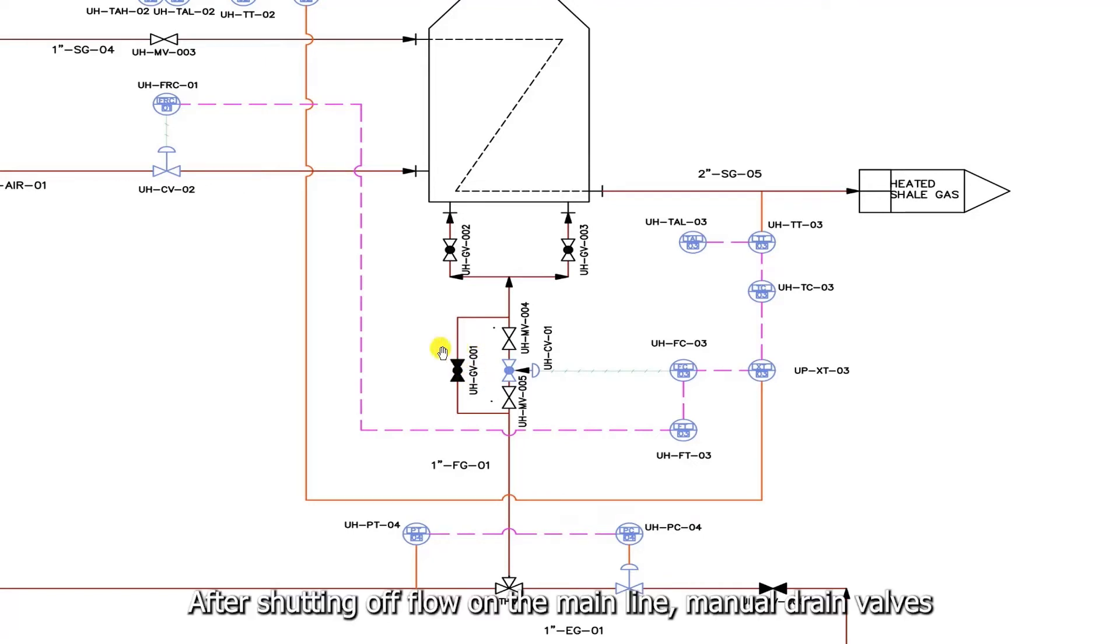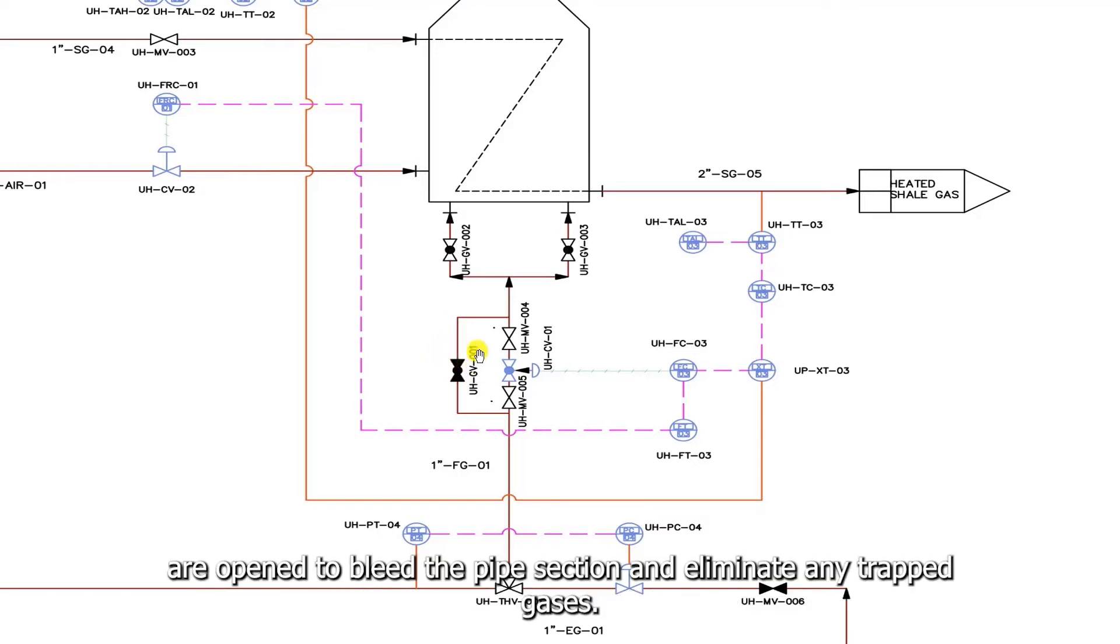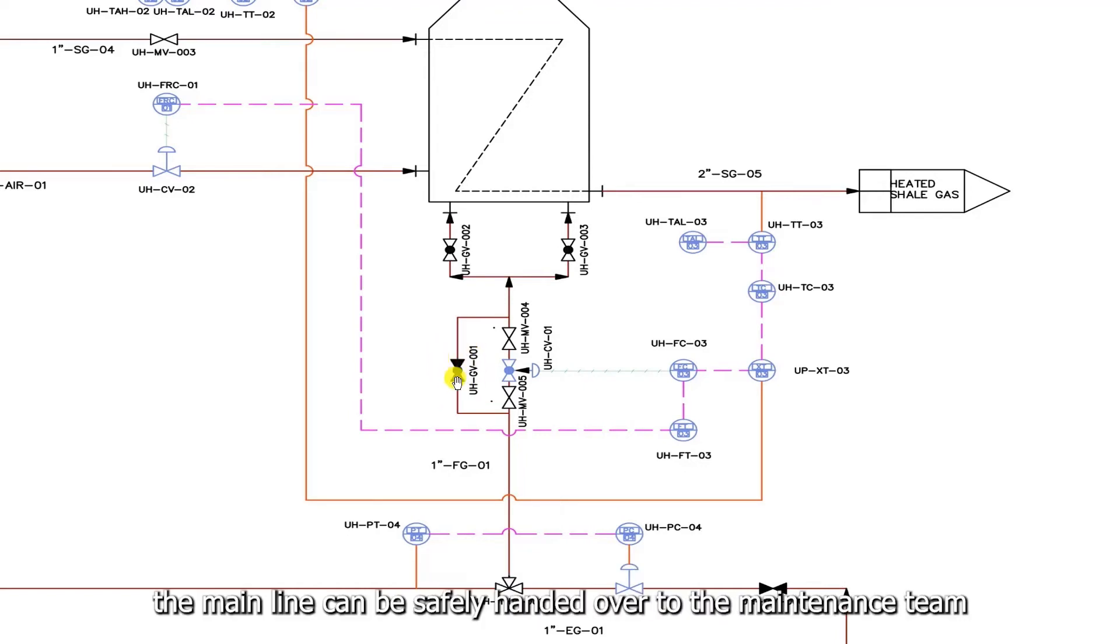After shutting off flow on the main line, manual drain valves, which are not depicted on the diagram, are open to bleed the pipe section and eliminate any trapped gases. Following this action, the main line can be safely handed over to the maintenance team for control valve replacement and repair.